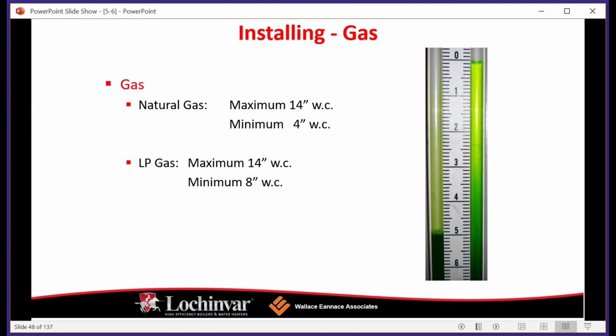So at 4 inches water column, the boiler's going to fire, but you're almost certainly going to have issues over time, because we can take 2 readings with a manometer. You can have your static reading, which is the amount of pressure that comes from your regulator to the boiler while the boiler is idle and the gas valve is shut. So if you come in and say, I have 4 inches of water column, great, but the boiler's off. What's going to happen when the boiler fires and that gas valve opens?